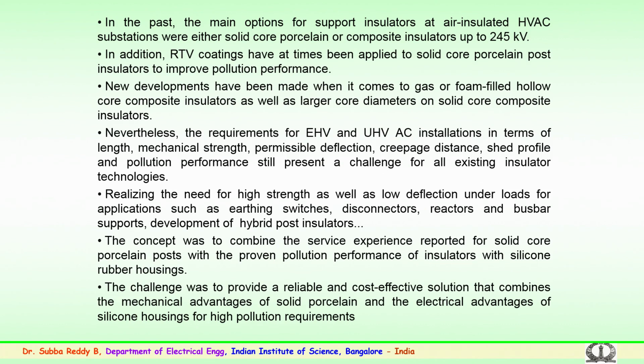Nevertheless, requirements for extra high voltage and ultra high voltage AC installations in terms of length, mechanical performance, creepage distance, shed profile, and contamination performance of bushings or post insulators still present a challenge for all existing insulator technologies, whether porcelain or polymer.